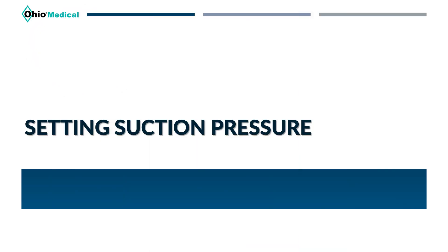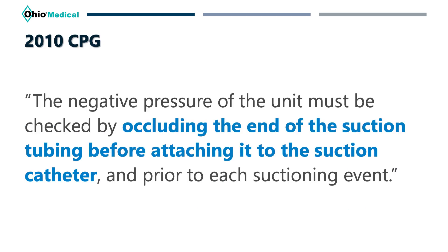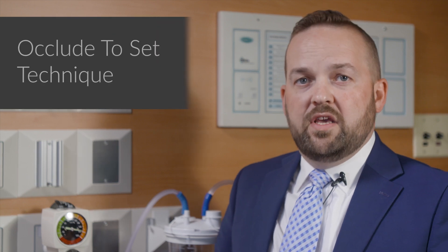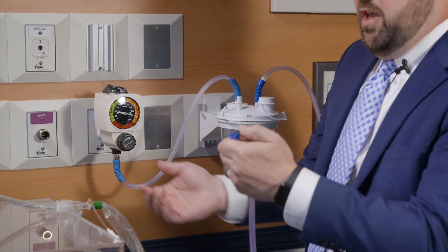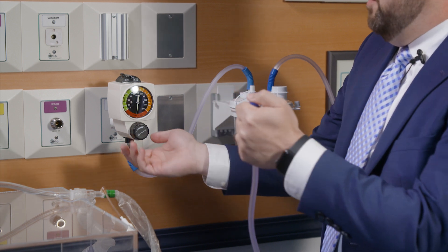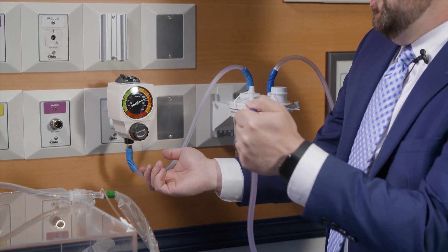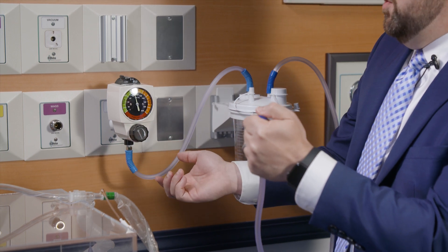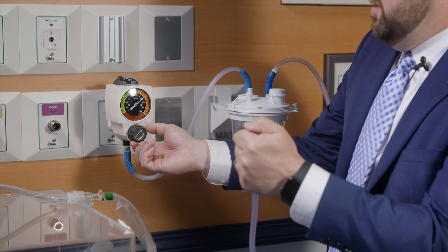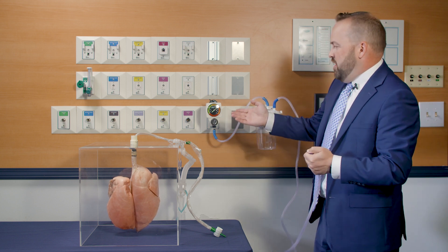Now that we've discussed what the suction pressure should be set at, how do we actually ensure the pressure is set appropriately? The CPG states that the negative pressure must be checked by occluding the end of the suction tubing before attaching it to the suction catheter and prior to each suctioning event — this procedure is referred to as 'occlude to set.' To demonstrate: go to the vacuum regulator and remove the tubing from the appliance you're using. Put your thumb over the end of the tubing and pulsate as you decrease the pressure on the regulator. For this example, I'm setting to 140 — suction pressure should start around 100 to 120, going no more than 200.